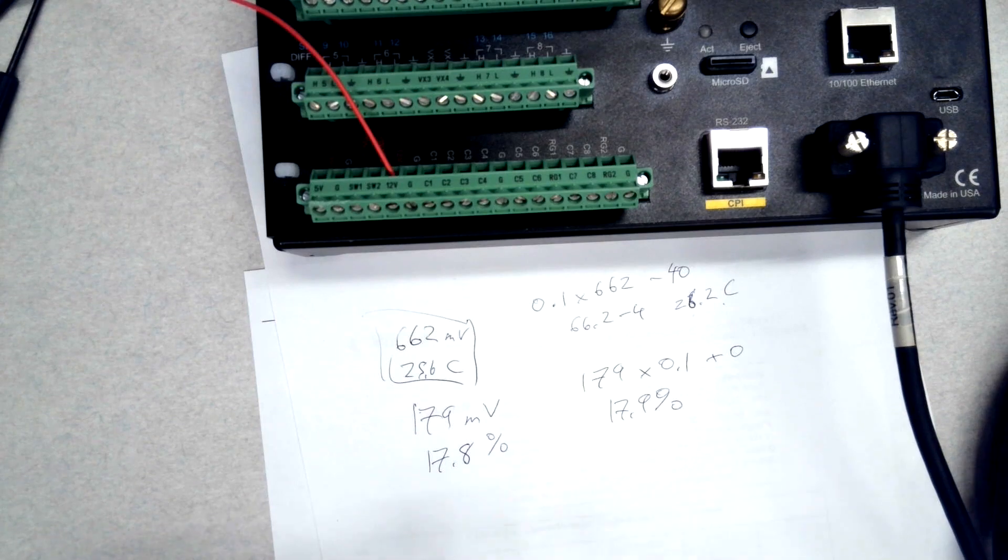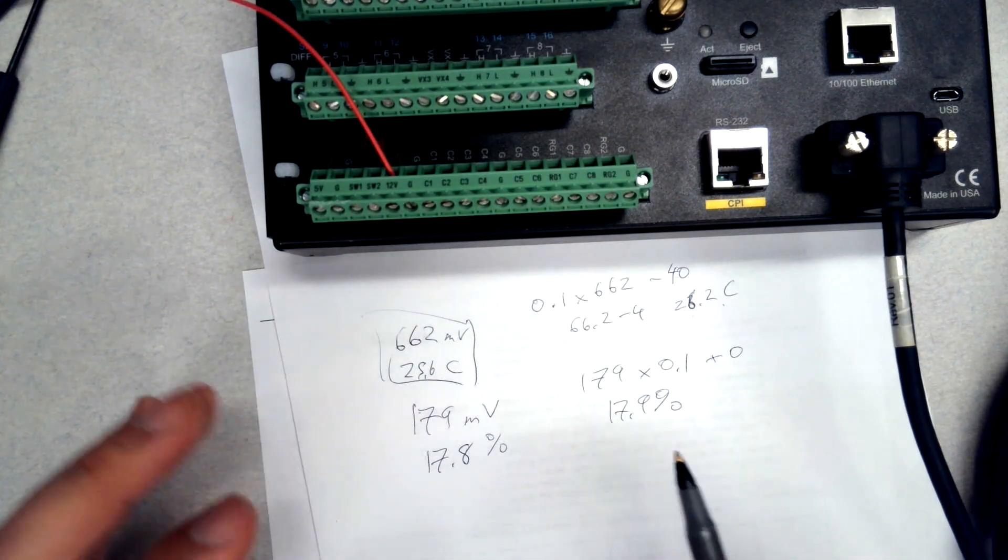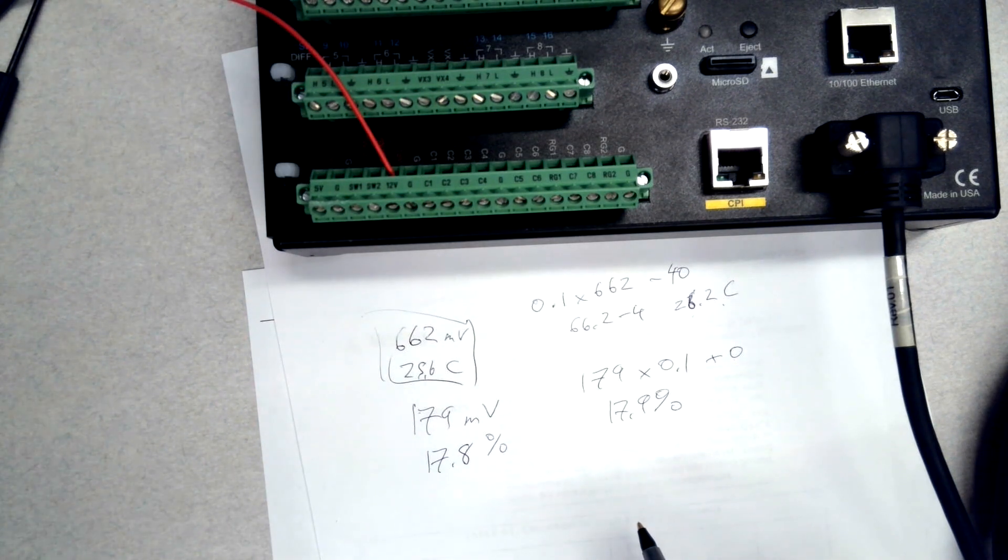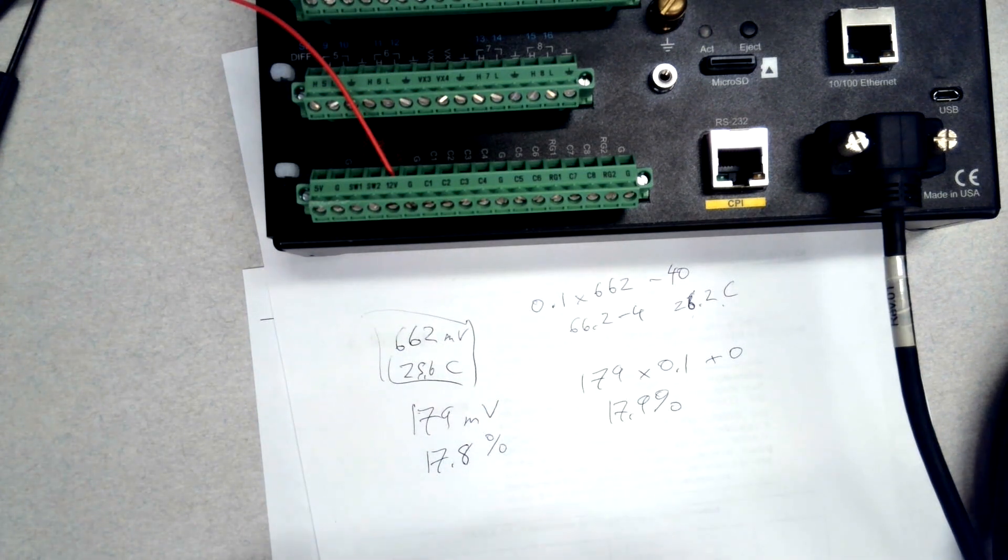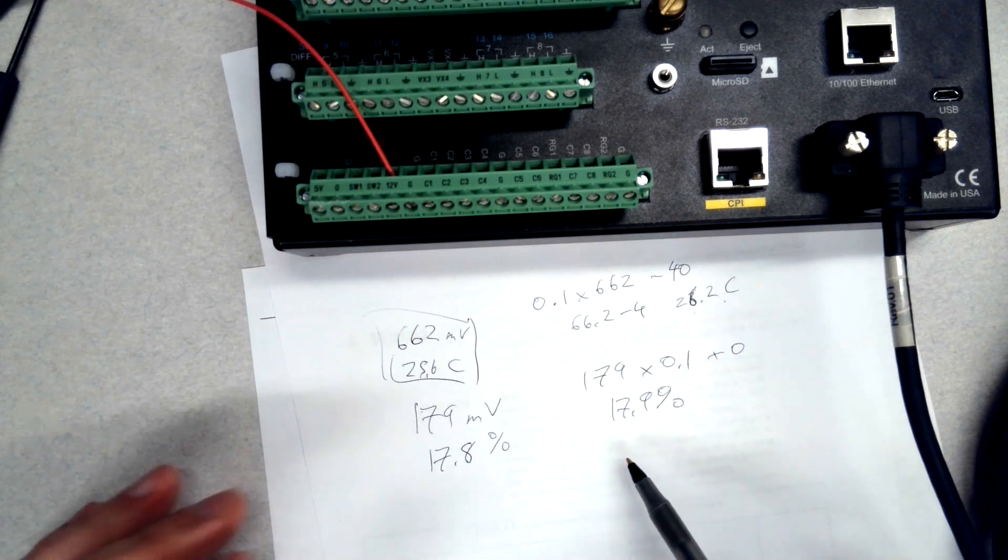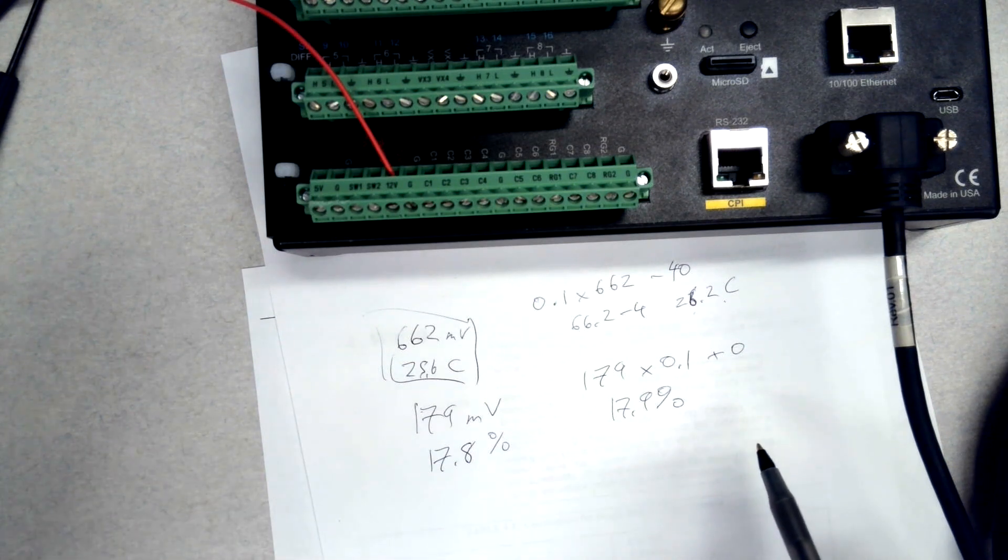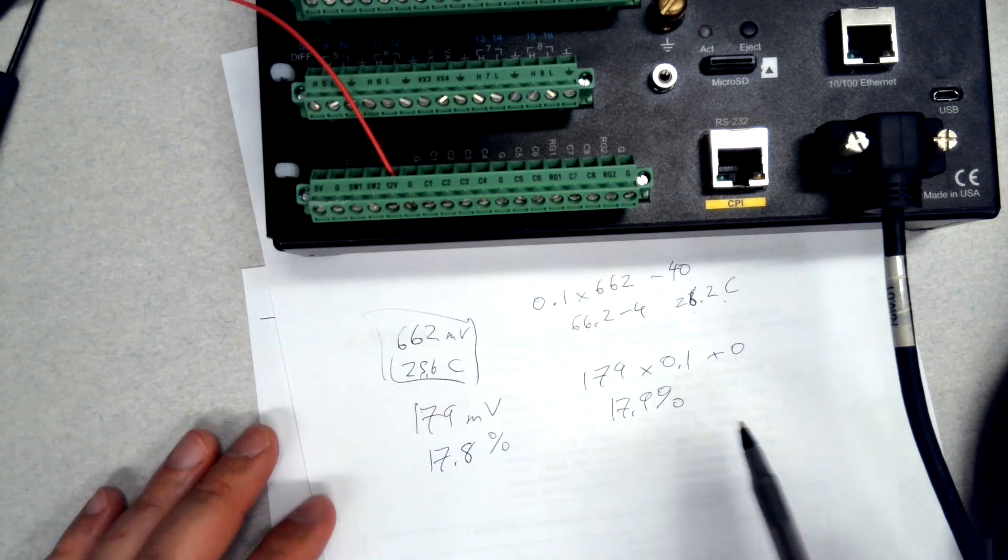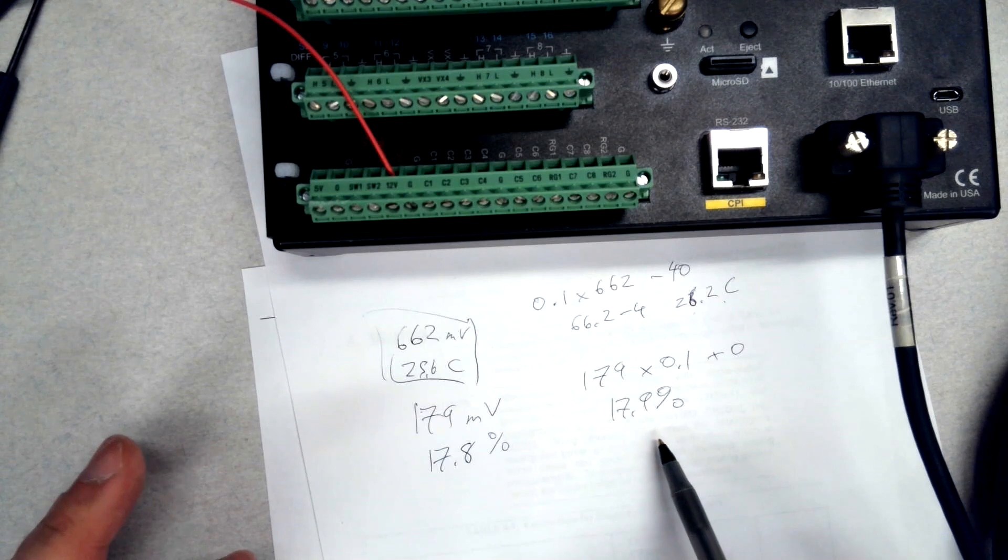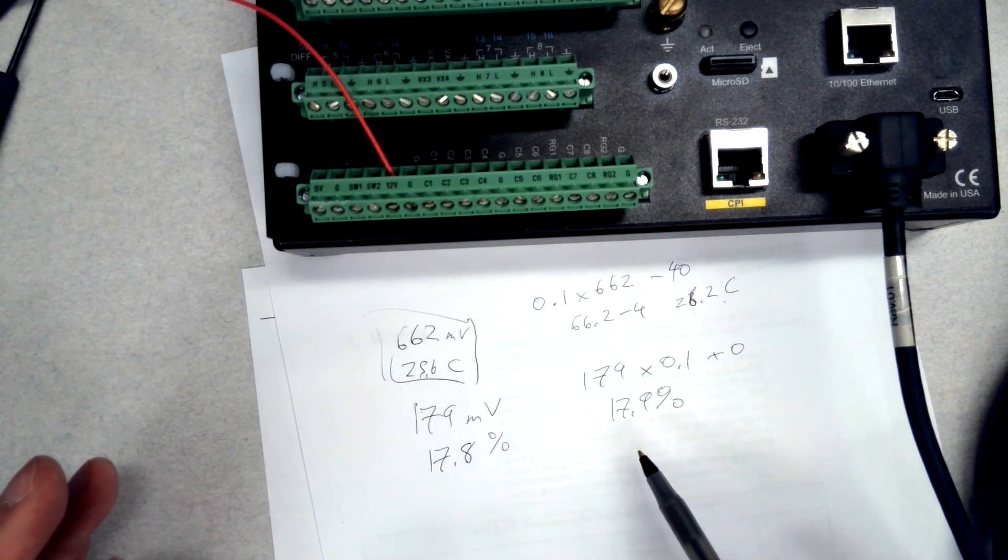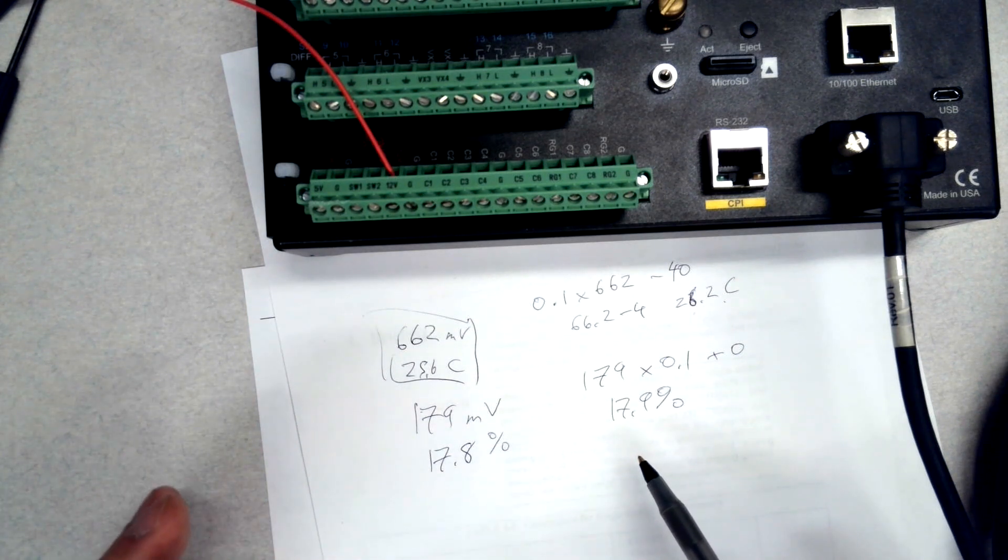If these readings do not look right, then you're going to have to compare the sensor to another sensor. If you've got another duplicate sensor, you could swap out the sensor if you suspect its readings are bad, or it could be a secondary sensor where you can co-locate it. A handheld temperature meter might get you roughly in the range, but again, the accuracy of it—you'd have to be mindful of the accuracy of the sensor connected to the data logger versus a handheld meter, because the difference can be quite a bit.